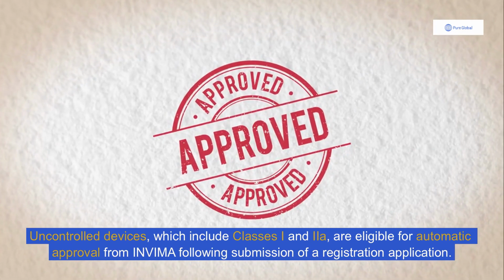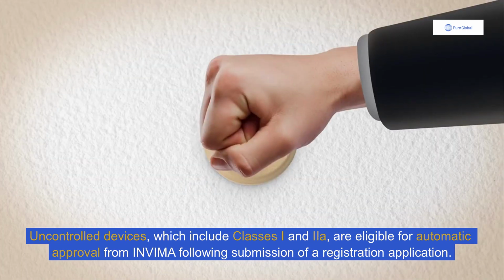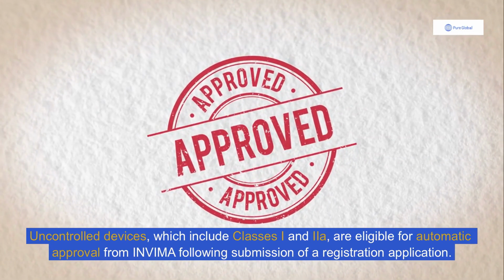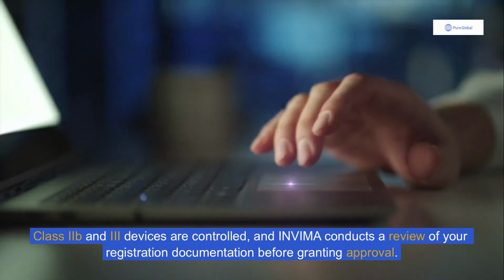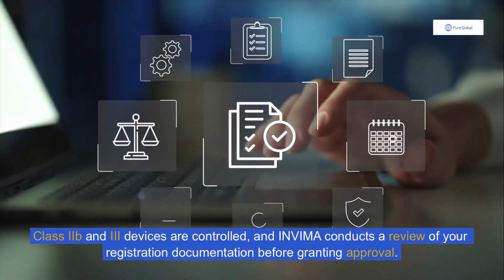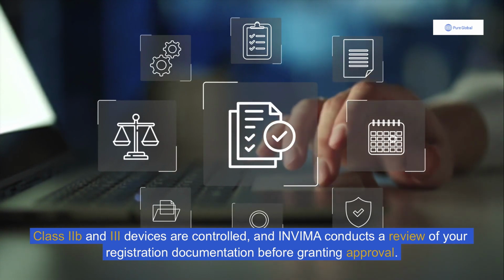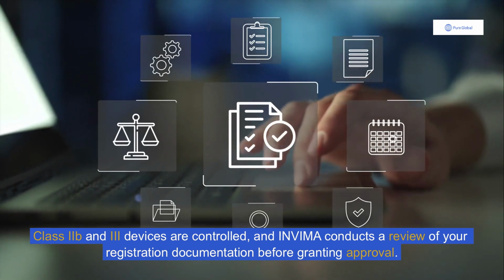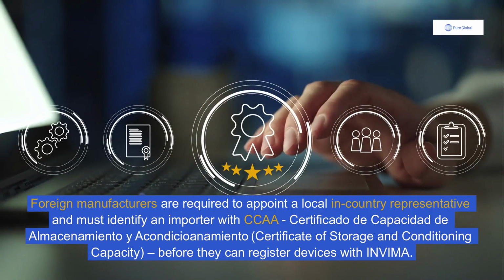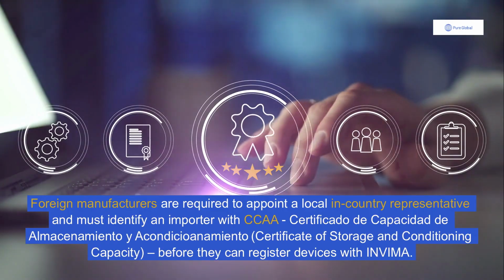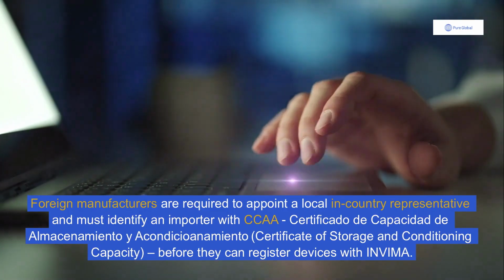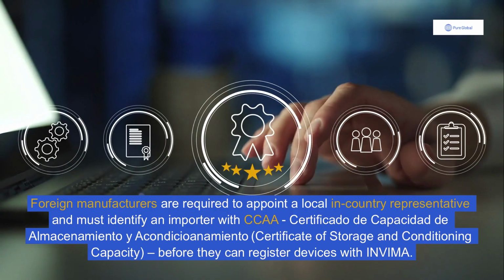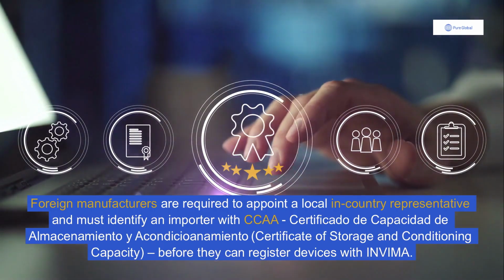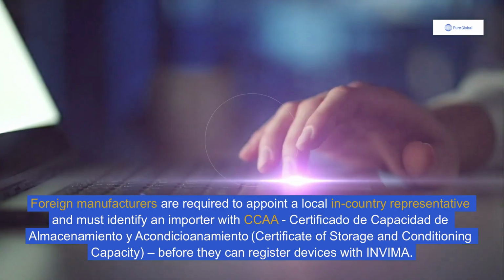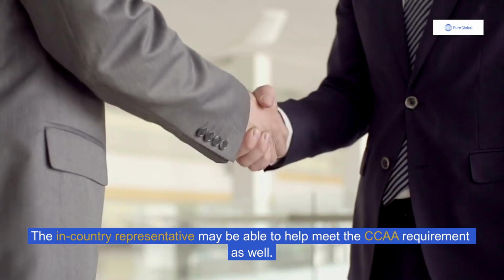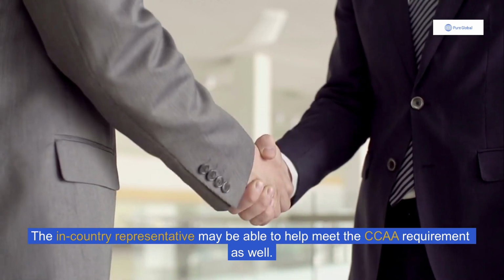Uncontrolled devices, which include classes I and IIa, are eligible for automatic approval from Invima following submission of a registration application. Class IIB and III devices are controlled, and Invima conducts a review of your registration documentation before granting approval. Foreign manufacturers are required to appoint a local in-country representative and must identify an importer with CCAA, Certificado de Capacidad de Almacenamiento y Acondicionamiento, Certificate of Storage and Conditioning Capacity, before they can register devices with Invima. The in-country representative may be able to help meet the CCAA requirement as well.